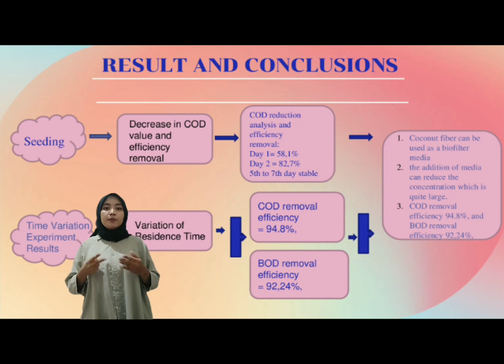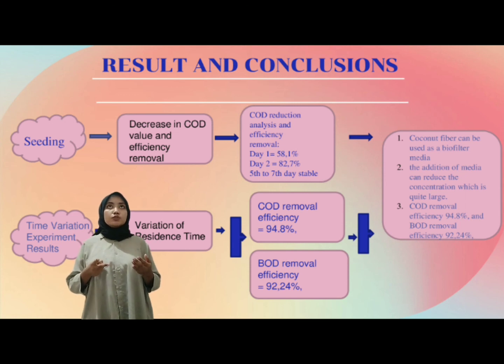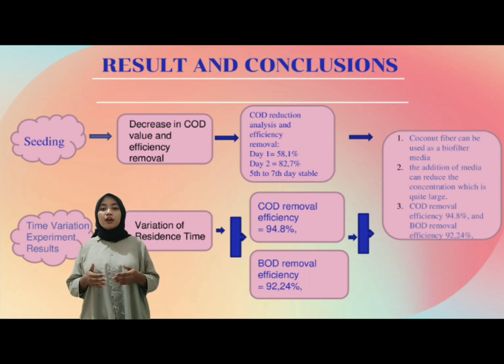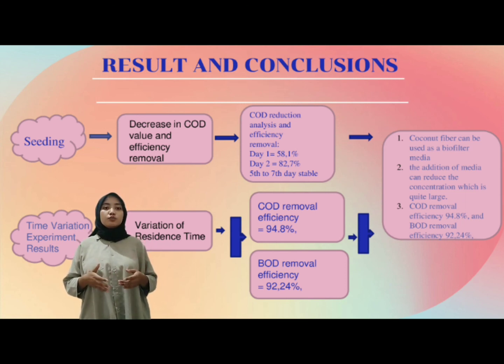With the addition of media as a place of attachment for microorganisms, it can reduce the concentration with a large difference compared to without using media, and the highest ability to remove COD and BOD concentration was at the processing time of 9 days with COD of 94.8% and BOD of 92.24%.